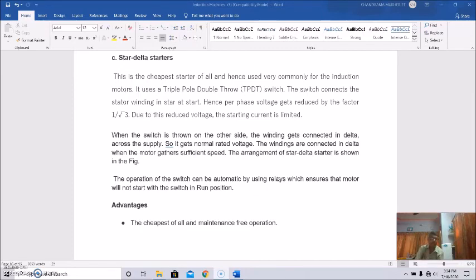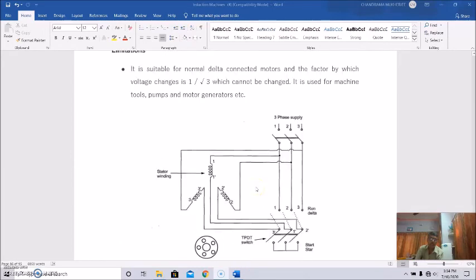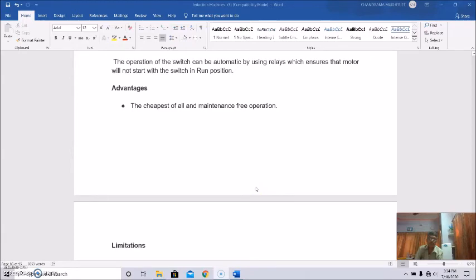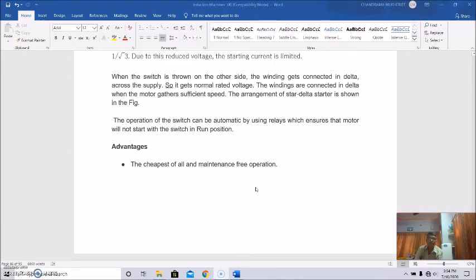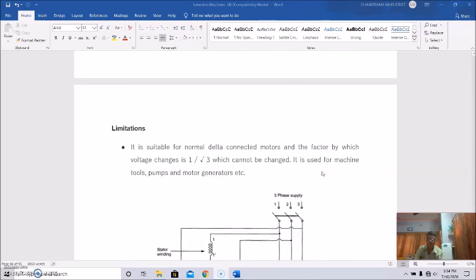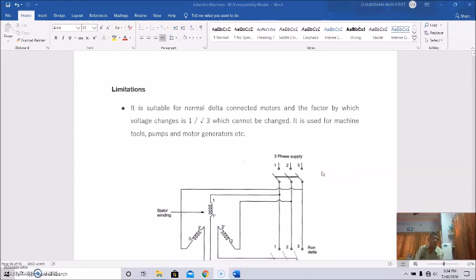And the arrangement of the starter is shown here. The operation of the switch can be automatic by using relays, which ensure that the motor will not start with the switch in the run position. The advantage of this type of starter is that it is the cheapest of all, and maintenance-free operation is possible. But the limitation is that it is suitable only for normal delta connected motors, and the factor by which the voltage changes is 1 by root 3, which cannot be changed. So it is used for machine tools, pumps, and motor generator sets.